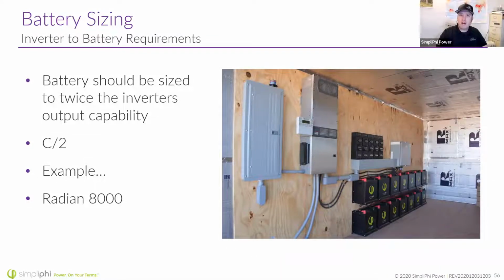I know that each of those Phi 3.8 batteries is capable of discharging at C/2. So if I have 3,800 divided by 2, that means each battery is capable of charging or discharging at 1.9 kilowatts. So I take my 8,000 watt Radian divided by 1,900, that's 4.2. I need to round up. That means I need at least 5 of our batteries in that system, because I can't tell that Radian not to discharge at any lower than what it wants to. So if you've got 8,000 watts being called to come out of that Radian, and you have less than 5 batteries, you're going to exceed the continuous charge or discharge rating of those batteries. In this example, there's a lot more than 5 batteries, so we know that we're good here.